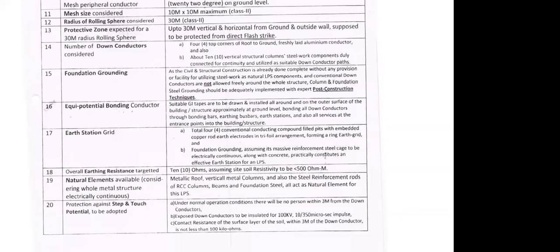Natural element consideration while doing this, as I said: metallic roof, vertical columns, and also steel reinforcement rods of RCC columns. But one thing we need to ensure here: if we want to use any building structure in the lightning protection system, then we have to ensure that during lightning, under any circumstances, no living object, man, animal, whatever it is, ever touches that particular body. If by mistake someone touches it, there may be a fatal injury or even death. So even if we want to use any existing structure of the building, we need to protect it, either with some camouflaging or some sleeves, to protect that live part so that if anybody touches it by mistake, he is safe.